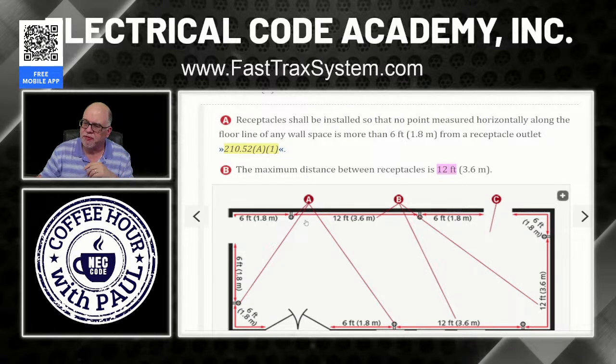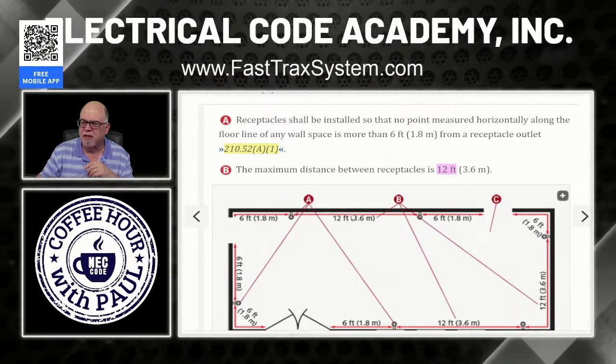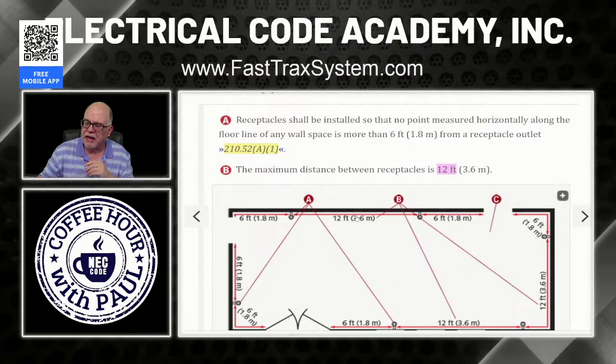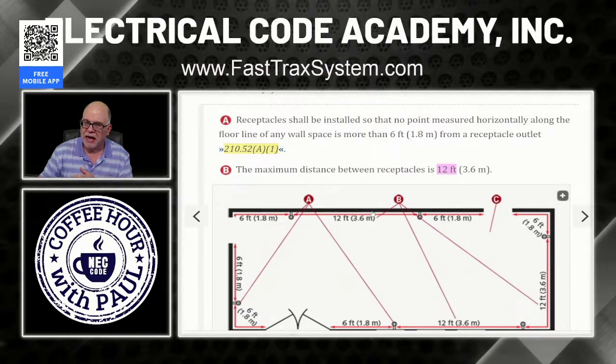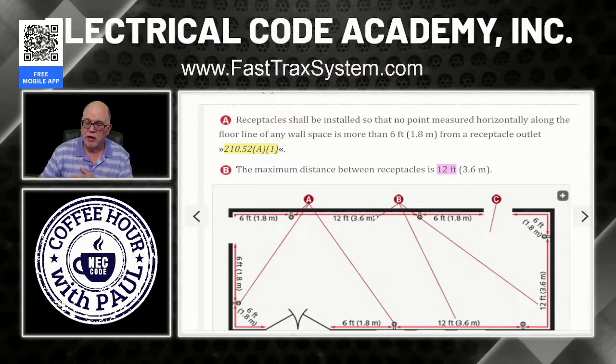Now, why 12 feet between this one and this one? Because if I were to go right here in the middle of these two, it's 6 feet and then 6 feet. I'm right in the middle. I am within 6 feet of this receptacle on the left, and I am within 6 feet of this receptacle on the right. So at this point of the wall, I am always within 6 feet of a receptacle. So if I go a maximum 12 feet apart anywhere in this wall line, if I go right here, I am within 6 feet of a receptacle. I wouldn't be within 6 feet of this one, but I am within 6 feet of this one. So I am compliant.